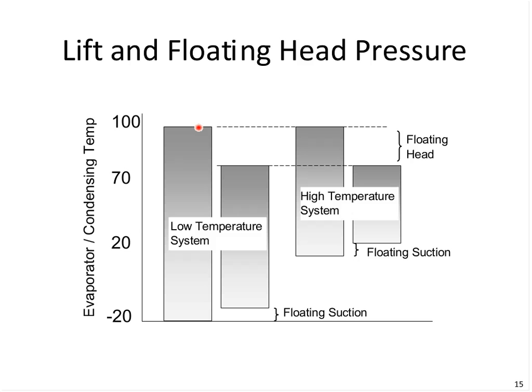On a really hot ambient day, we may be condensing at near 100 degrees. And of course, we're trying to maintain minus 20 because of that extreme day. But notice here, we have a milder day or wintertime. It could be below 50 degrees ambient. We could condense somewhere around 70, 75 degrees. And we may not always need minus 20 degrees. Maybe minus 15 would be sufficient to maintain product temperature.